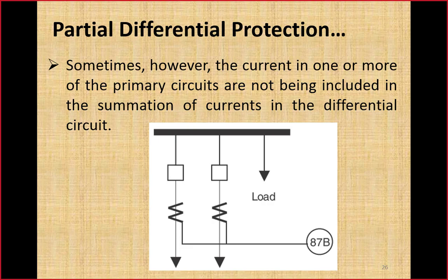So due to this reason, it would add extra expense to include this load in the differential protection. So normally we can ignore this. The pickup setting of the overcurrent differential or the voltage setting will be set according to this leakage current, because this load, which has been tapped to fulfill the local requirement of the substation, is almost negligible with respect to the load carried by these transmission lines or transformers.